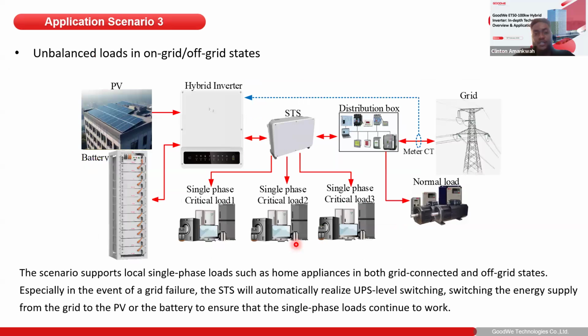The third applicable scenario that we can also think of is the unbalanced load in on and off-grid state. Like I said, the inverter itself is a three-phase system, but the inverter comes with 100% unbalanced output. Now, what does this actually mean to the end user? With this, aside from having a three-phase load connected to the inverter or the STS, you can also have three different single-phase load demands connected to the STS units.